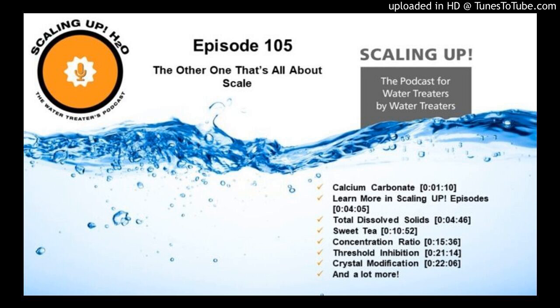So it's very important we understand what our water is telling us, what products we're putting in the system, making sure those things match up so we can keep the system clean as heat transfer efficiency managers. So what are some of the tools that we use to help not scale up a system? Well, folks, if you have a cooling tower, I guarantee you have a bleed set on that cooling tower.